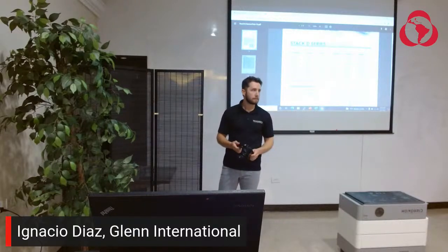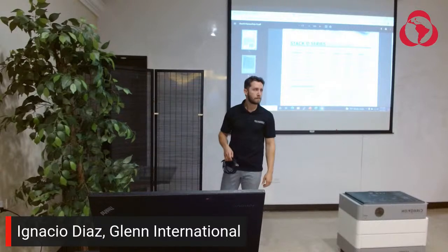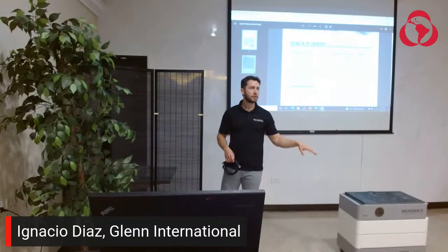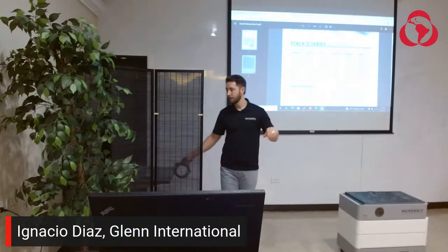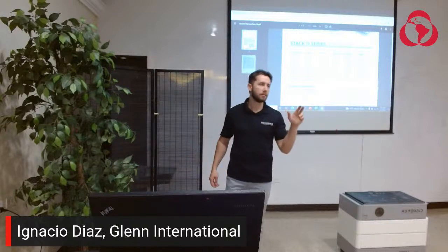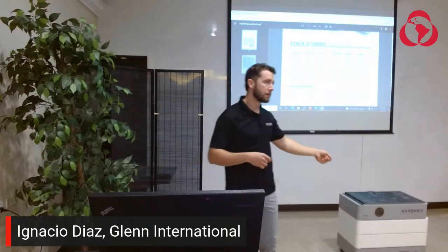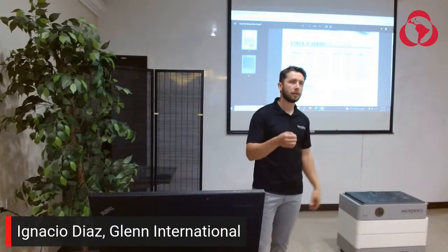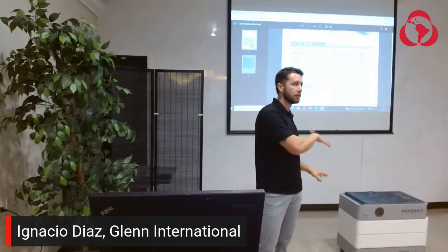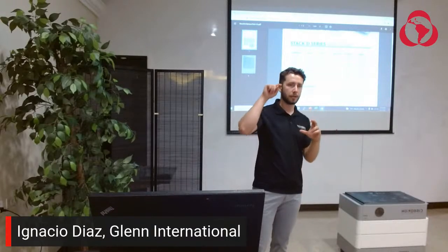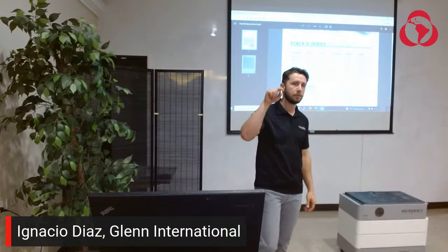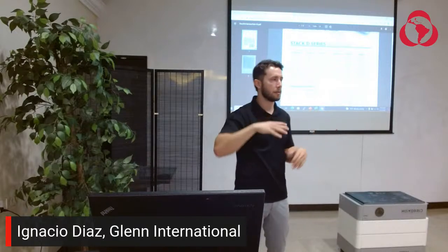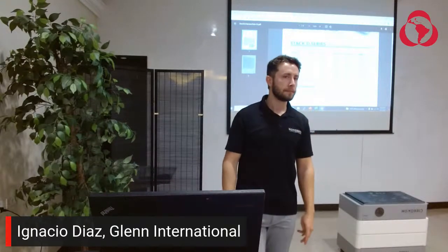So do you have to set parameters on Solar based on size, PV, and so on? No, we have communication with Solar already. When installing with a Solar system, there's just a little switch you set the battery to Solar, and on Solar it's just the BMS protocol 00, and it automatically loads and communicates everything to match the size of what you have stacked.